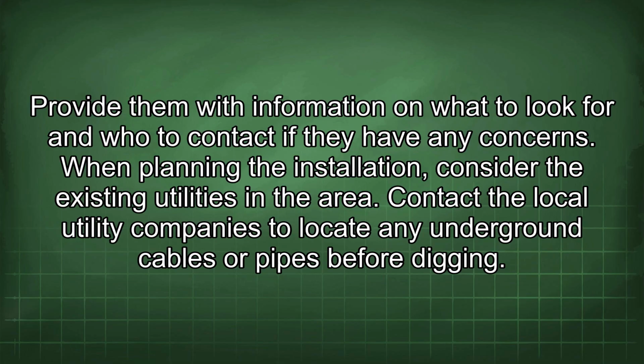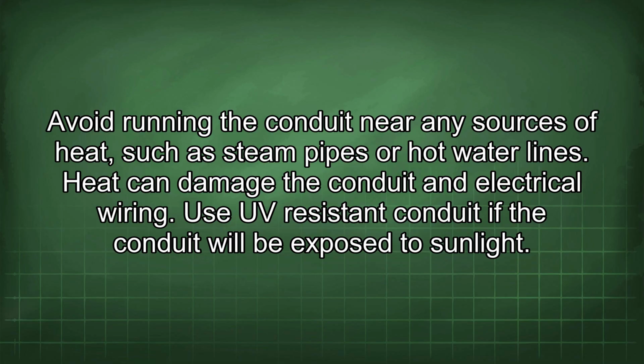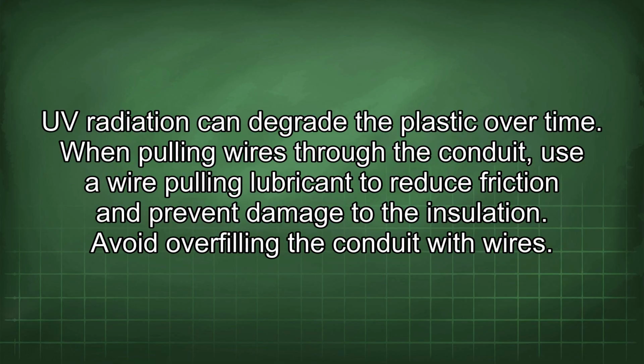When planning the installation, consider the existing utilities in the area. Contact the local utility companies to locate any underground cables or pipes before digging. Avoid running the conduit near any sources of heat, such as steam pipes or hot water lines. Heat can damage the conduit and electrical wiring. Use UV-resistant conduit if the conduit will be exposed to sunlight. UV radiation can degrade the plastic over time.